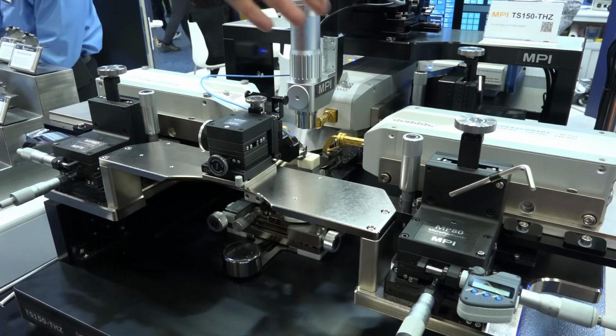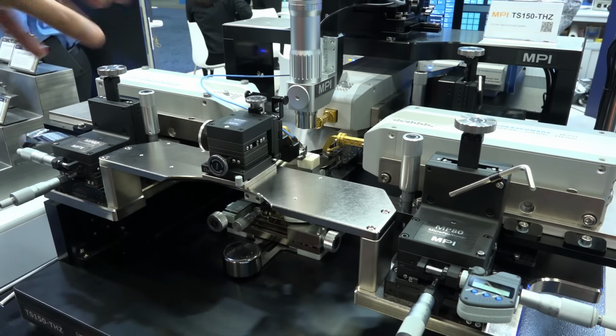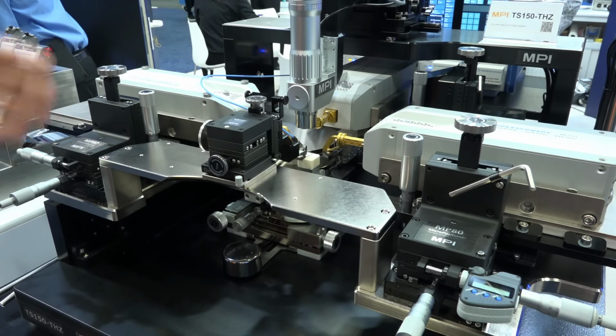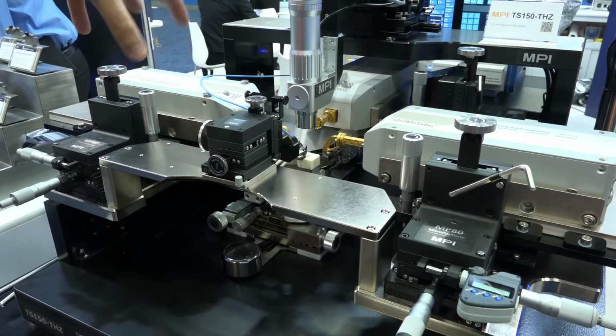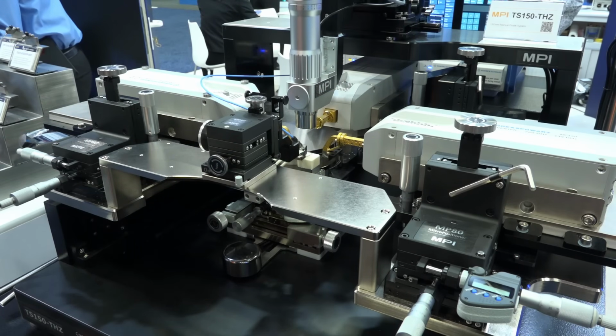And here, it allows you to have a complete 3-port solution, despite the fact that this is such a compact probe station, allowing you to do things like mixer conversions, all with individual remotes that are attached to it. Now, don't get fooled by the fact that this is a manual probe station. It still has all the digital measurements. You can still do very sophisticated calibrations on this, it's easy to use, and its compactness really does make a difference in scenarios where you don't have a lot of room or you won't have many probe stations next to each other.